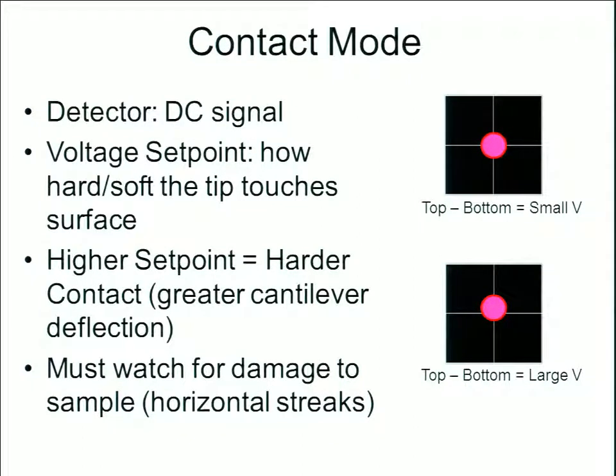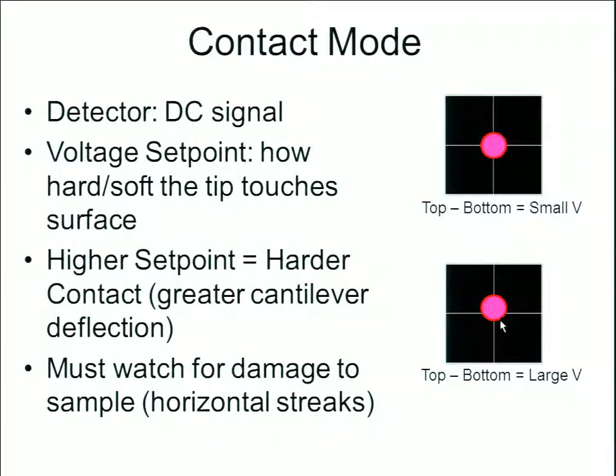The higher the set point, the harder the contact — in other words, a greater cantilever deflection. We are pressing the cantilever harder to apply a greater force down to the sample. When you do this, you need to watch for damage to your sample, which would look like horizontal streaking in your image once the scan is done. A lower set point would have a small voltage, and a higher set point would have harder contact and greater cantilever deflection.